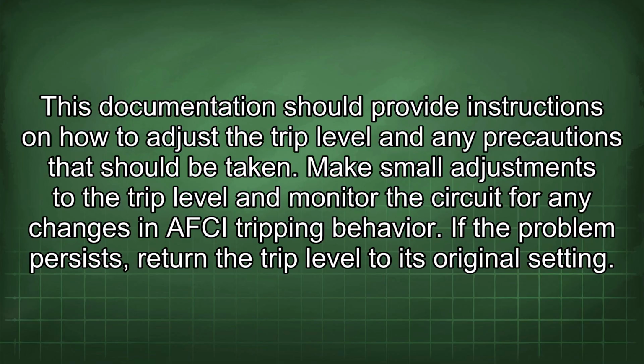Make small adjustments to the trip level and monitor the circuit for any changes in AFCI tripping behavior. If the problem persists, return the trip level to its original setting.